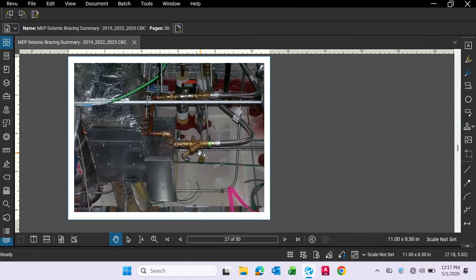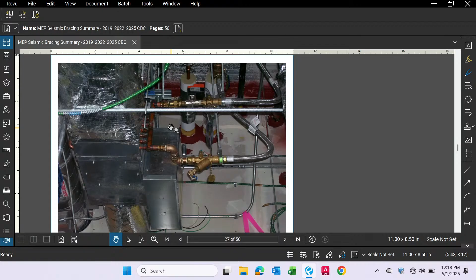So I showed you an earlier photo of the failure at the connection of the piping to the coil. This is one way where they address the relative displacement, by adding a flexible connector here. That way there's a lot of movement that can be had between the component and the associated piping. This is another picture solution for piping overhead into the equipment. You see these braided hoses. They allow a little flexibility, so that takes the stress off the nozzle on the connection.